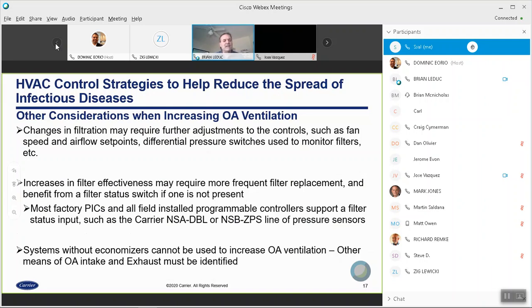Most of the factory PICs, if they don't have them already, are designed to accommodate them. So the last one is kind of an obvious point, but if the system doesn't have an economizer, you can't really use it to increase OA ventilation. So other means of outside air intake and exhaust are going to have to be verified.